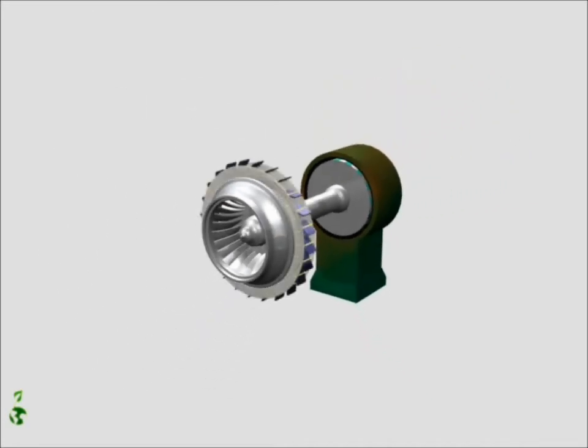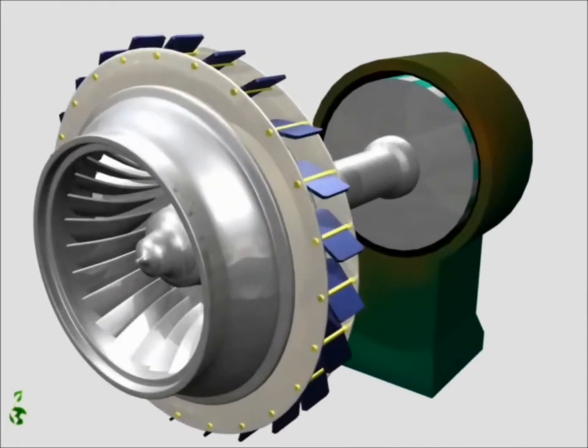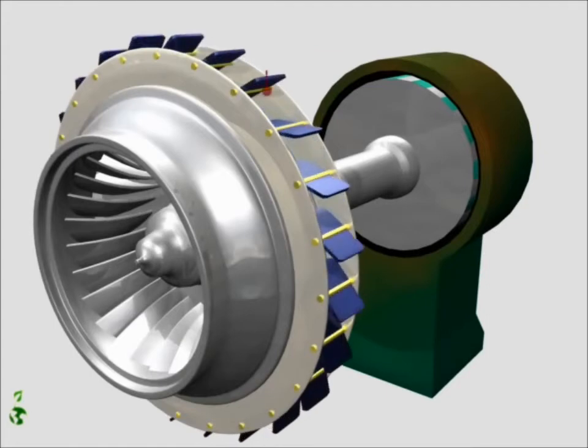The guide wheel surrounds the runner. The setting angle of the guide vanes can be adjusted to meet fluctuating power demands or to cause the turbine to spin at a constant speed at changing water levels.